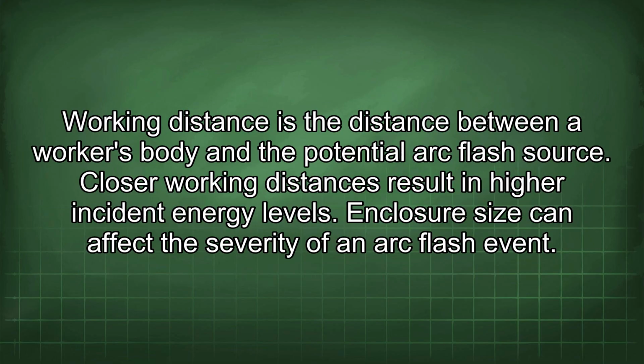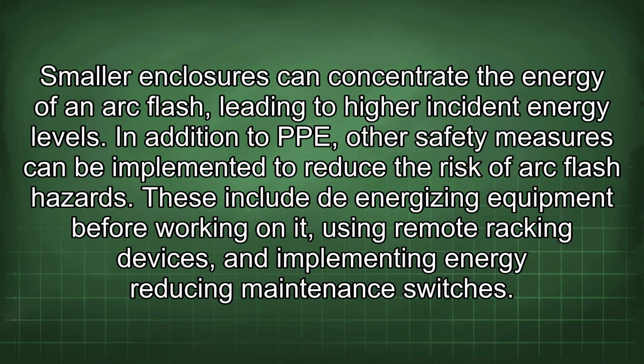Working distance is the distance between a worker's body and the potential arc flash source. Closer working distances result in higher incident energy levels. Enclosure size can affect the severity of an arc flash event. Smaller enclosures can concentrate the energy of an arc flash, leading to higher incident energy levels.